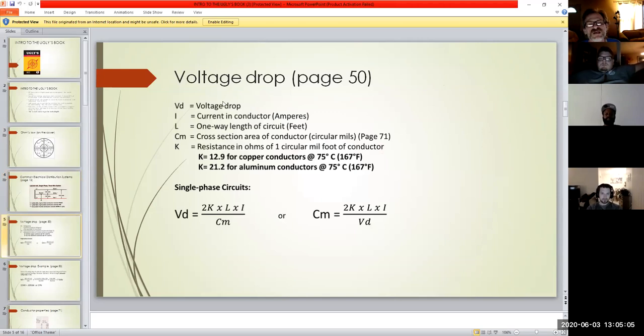This one's an important calculation, because voltage isn't infinite. If you have a good run and you bring wire out 100, 200, 300 feet, this calculation shows how much loss you're going to get over that amount of line. They even show whether it's copper or aluminum.